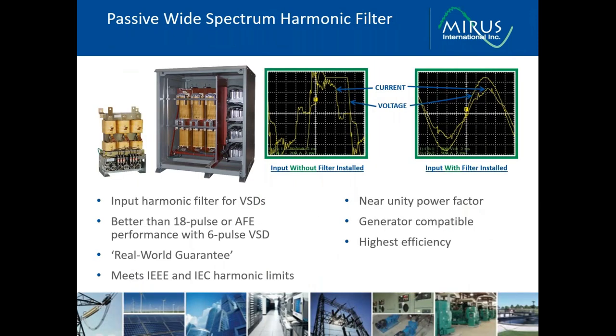The wide spectrum harmonic filter, or WSHF, is an input harmonic filter to treat harmonics generated by variable speed drives. As a simple passive device, it outperforms more complex solutions such as multi-pulse drive systems, active front ends, or active harmonic filters. It's been developed into the most reliable and best performing filter on the market. It'll improve the power factor by removing the harmonics, and at full load on a diode bridge application, the power factor will be near unity. It's generator compatible because the capacitor bank is designed to introduce very low levels of capacitive reactive power. And it has the highest efficiency of all of the solutions that would be used to treat harmonics.